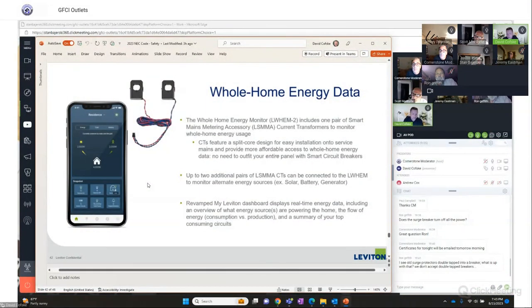But I guess to answer that question, when the surge goes into your house, you should have that on a dedicated breaker. Probably the reason why somebody double tapped it and shared it with another breaker is they didn't have enough room in the panel, but they wanted to add surge so that it would do some protection. I don't know if the result of sharing it on another breaker is the best thing. Will the surge be doing what it is intended to do or not? Gotcha. Thank you. But they should be on dedicated circuits. My understanding is everything should be on a dedicated circuit.